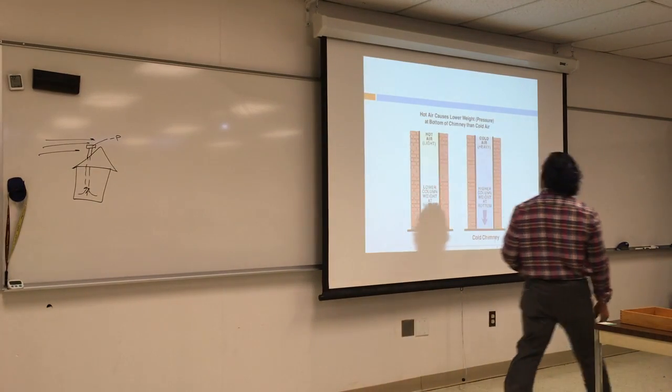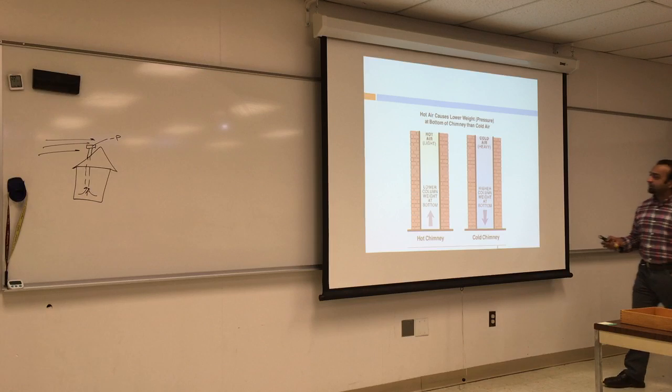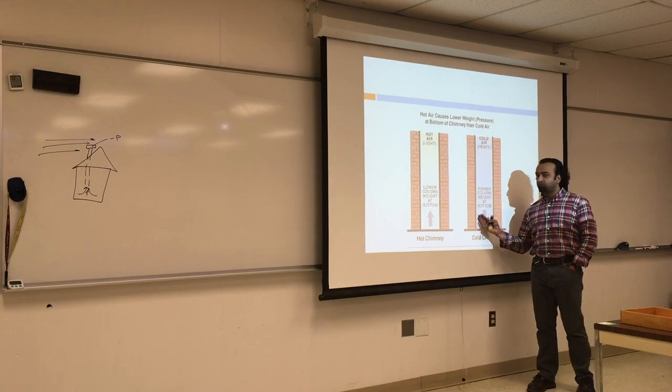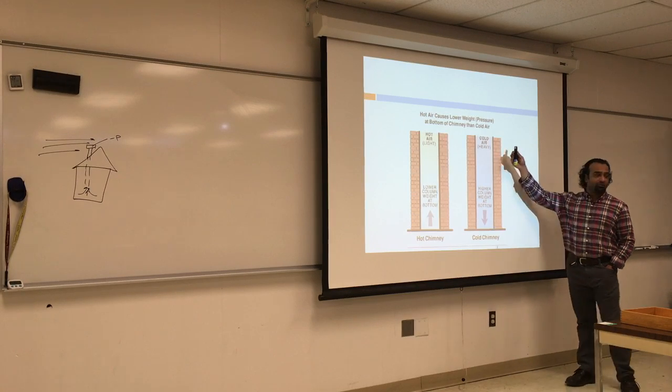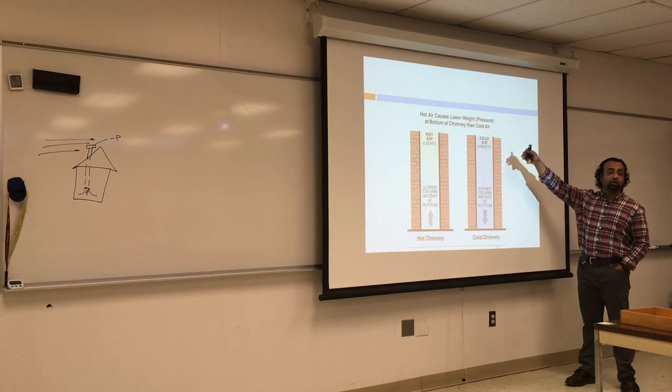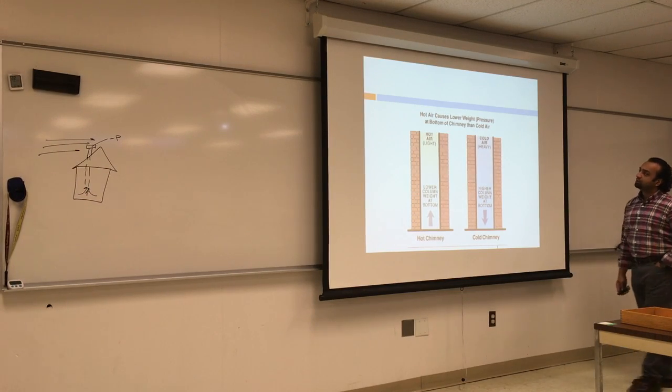We talked about that, hot air and cold air. And how if you have a cold day, you might have a lot of heavy air in the chimney, so it will be easier for the hot air to rise up and vent. But if it cools down before it goes out, it's not going to go outside and will just accumulate in your chimney.